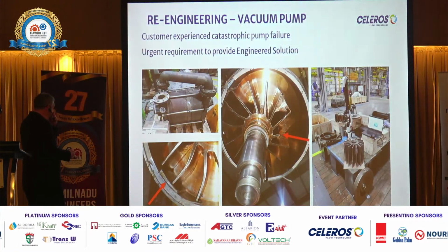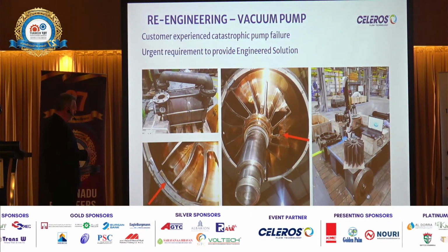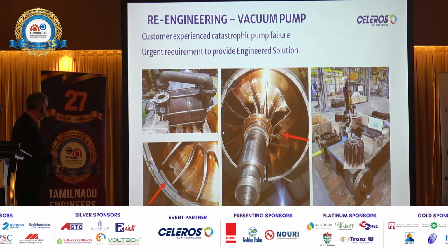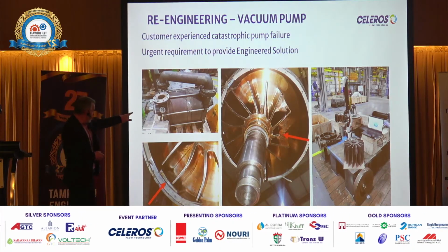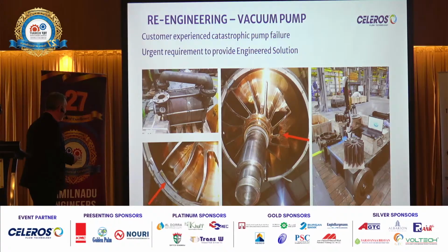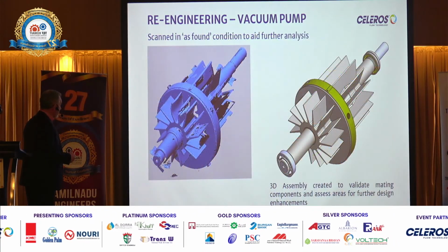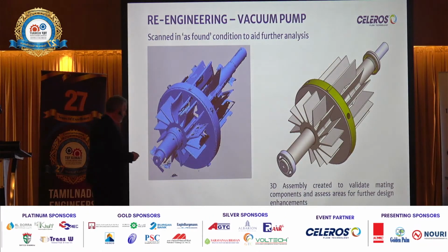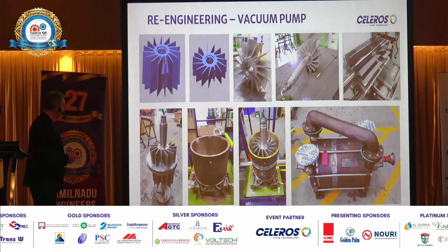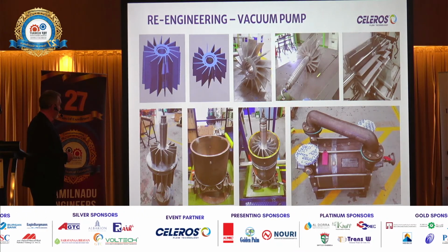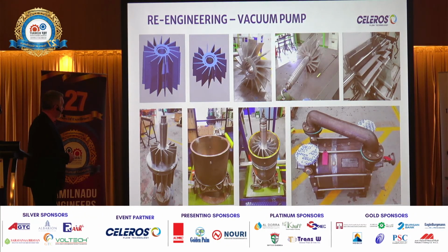Vacuum pump, it doesn't need to be a pump. This is one we completely reverse engineered the internals. We kept the discharge suction end and the crossover, that was all kept. And there's a raw scan here on the left. On the right is the 3D solid model. Again, that generates all the drawings. And then this is us building up the new rotor.